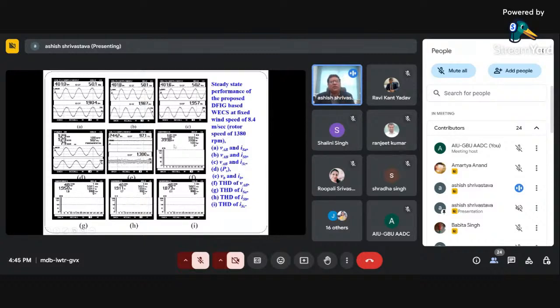Voltage THD will always be lower, but as per the IEEE standard, you have to maintain THD less than 5% for all three phases. This is for phase A, phase B, phase C. You can see that THD is 4.8%, 4%, and 4.6%. These results have been taken from the Fluke power analyzer, and as you can see, sinusoidal voltage and sinusoidal current have been maintained throughout. This is also showing how much active and reactive power there is, and your DPF here is 1.